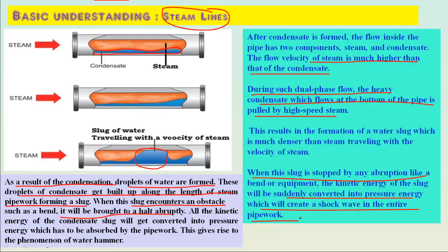When the slug is stopped by an obstruction like a bend or equipment, the kinetic energy of the slug is suddenly converted into pressure energy, which creates shock in the entire piping network, and can easily be heard as lots of noise in the piping system.